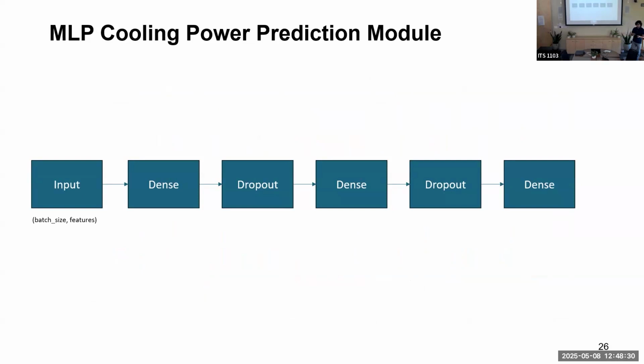So the next step would be to have a model for our refrigeration facility. Here we've already experimented with some physics-based models, so having a cooling load and then optimizing which compressors are running, how the evaporators are running, and then what would be the cooling power for the facility. But we've also tried to use a data-driven model here as well.